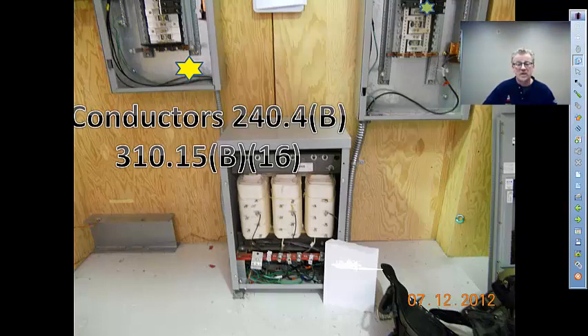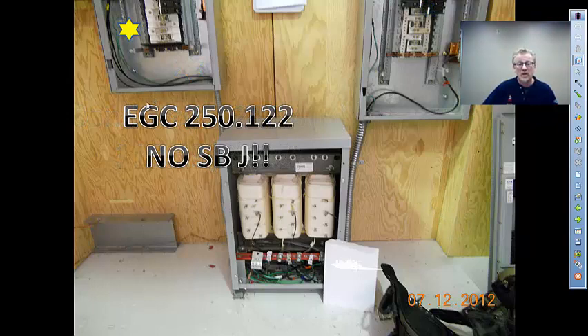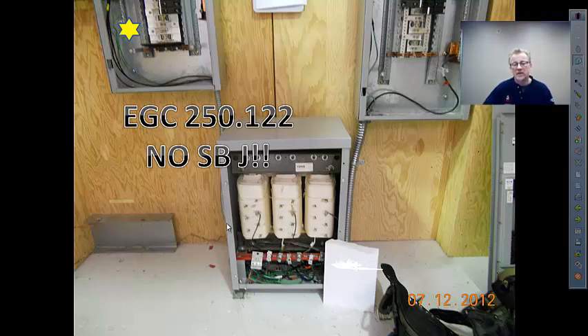The next thing we need to do is realize we have an equipment grounding conductor. The case of the transformer will have to be grounded. Maybe the wiring method will do it. Maybe not. The flex, which is installed for flexibility after installation, cannot be relied upon for bonding and grounding. That's 250.118. So, transformer vibration isolation may or may not be needed for flexibility after installation. Sort of depends on your AHJ. Certainly if your specs tell you to. Pull an equipment grounding conductor sized to 250.122.